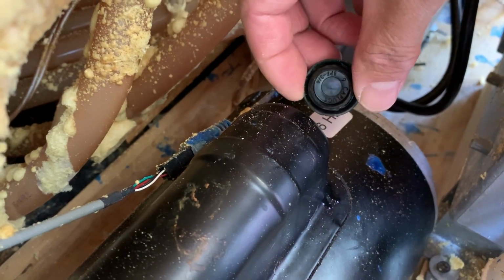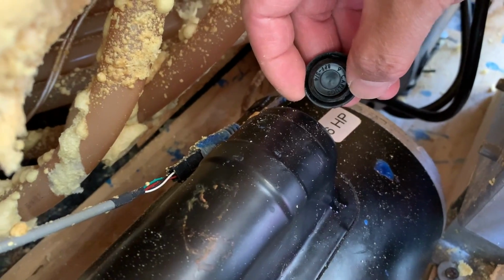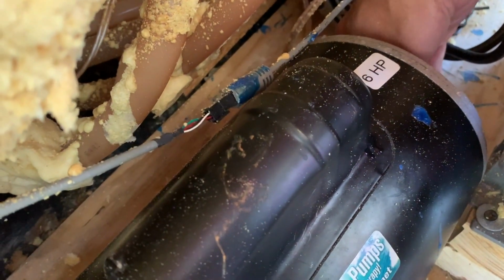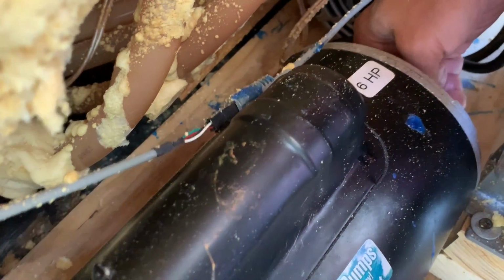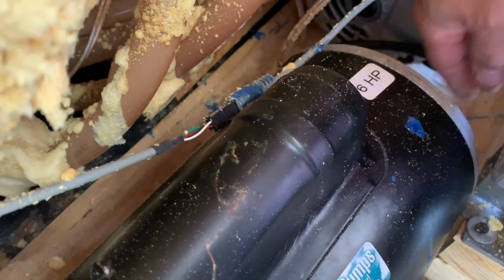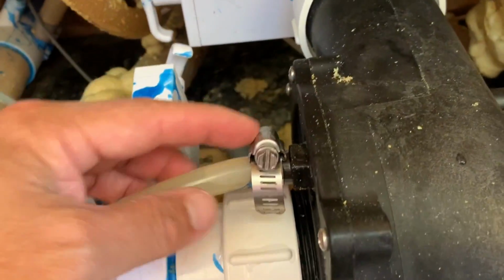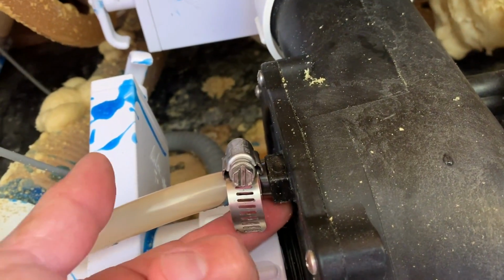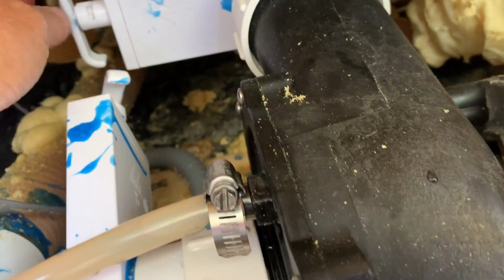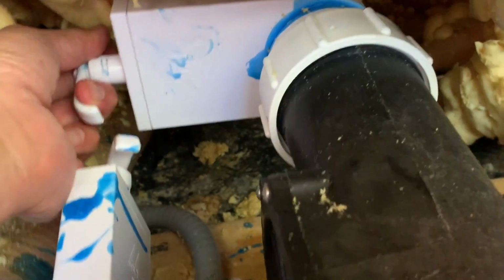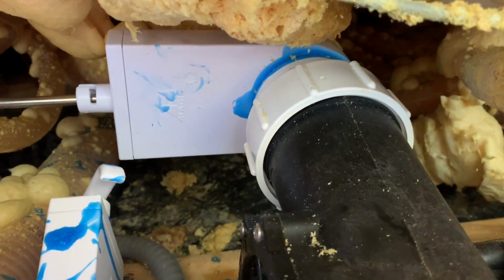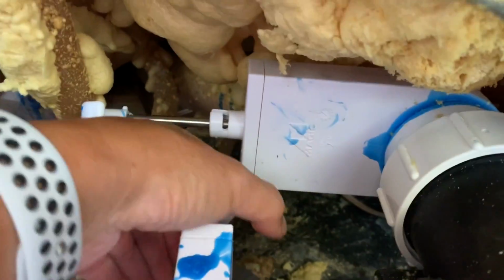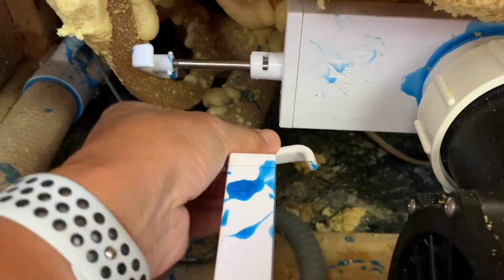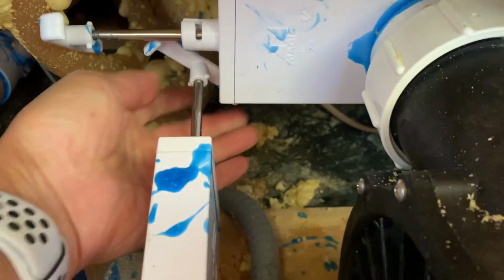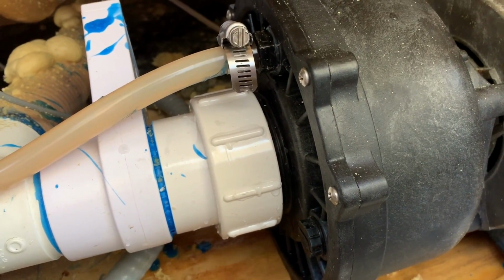Before I forget, I'm going to have to snap this plastic cap back on the end of the electric motor, which is down here. Fortunately, it just snaps right on. Okay, so I've got this reattached with the new hose clamp. This was leaking initially, but now it's stopped since I've tightened this clamp. Let's see if these gate valves will open up. We'll look for any leaks. So far that looks good. Let's open up this one. You can hear the water gurgling now. And I don't see any leaks either.